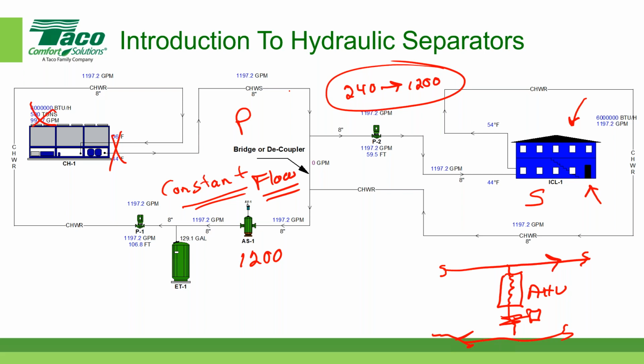Yeah, and in terms of classic basic design, the load on the secondary side varies, or let's say the flow is a better term, the flow on the primary side remains constant. So the flow on the primary side is constant, and the flow on the secondary side is variable. Big V over here for variable flow. And under those circumstances, assuming that at 100% load is equal to 100% capacity, that would be the maximum flow at 1,200 gallons per minute. And then the minimum would be based on some other criteria, perhaps whatever the pump could withstand for minimum flow, which might be around 20%. Okay? Yep.